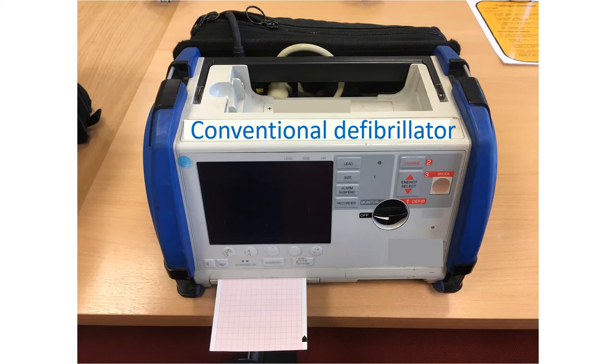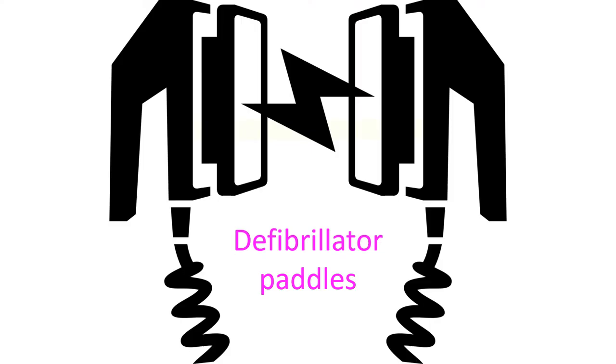In conventional defibrillator, as automatic rhythm analysis is not available, the trained operator has to decide whether shock is advisable or not. But most modern defibrillators also have an AED mode for emergency use. Proper application of patches or paddles is necessary. If paddles are being used, an adequate amount of conducting gel has to be applied over them for proper delivery of shock. Paddles should be firmly applied for the same purpose as well as to minimize skin burns.